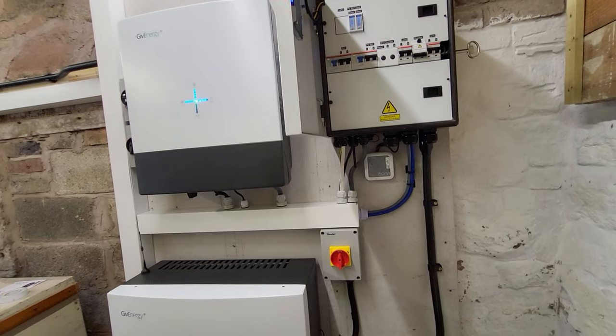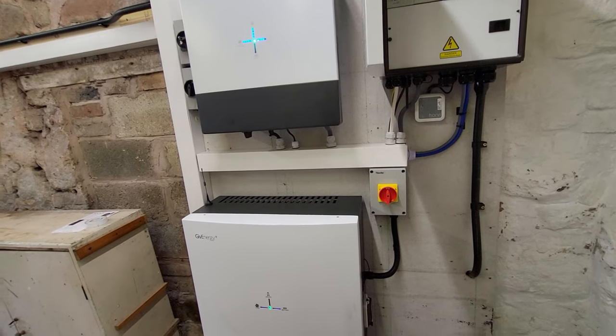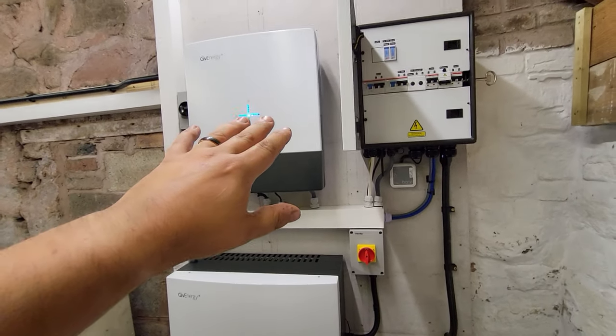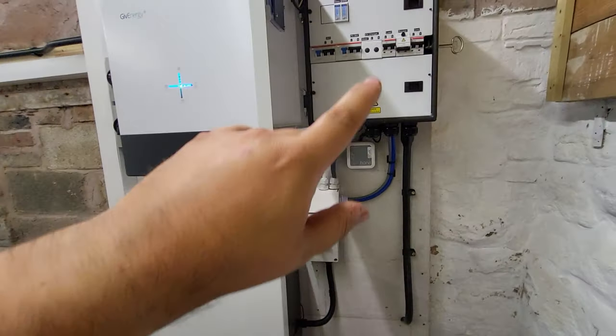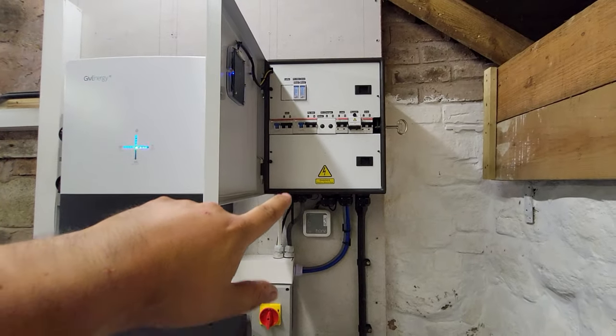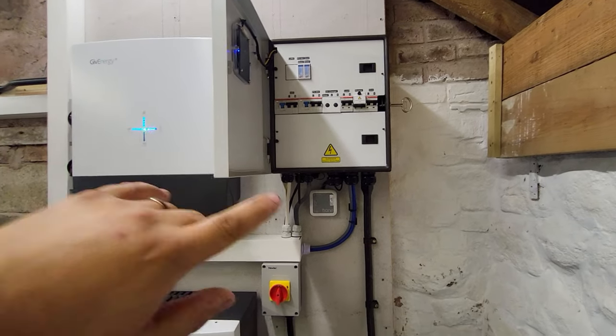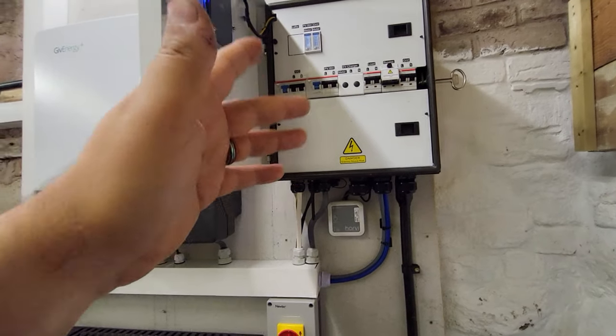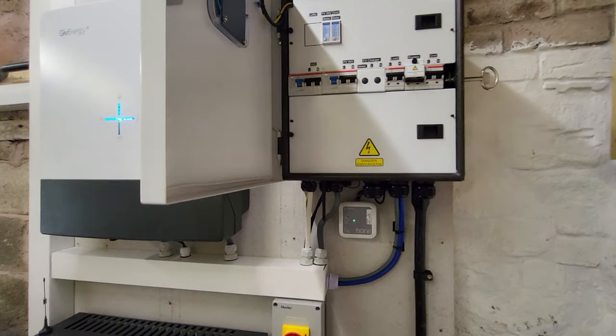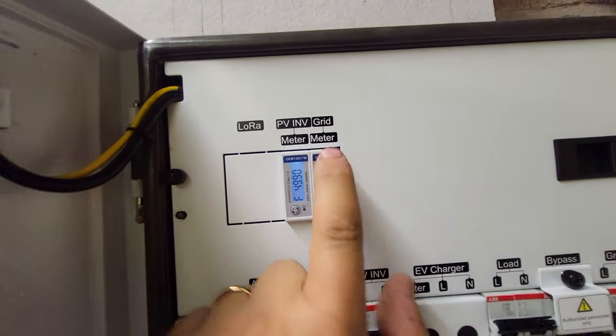So there has to be an element of understanding from the customer that it's not just going to run everything, because there could be situations where the solar generation isn't enough to cover the house loads alongside the battery. Basically, it does alarm. You can transfer that alarm as well via remote contact links over to the house should you wish, but it does the notification on the app too, pretty instant, so the customer becomes aware that they've got a problem.